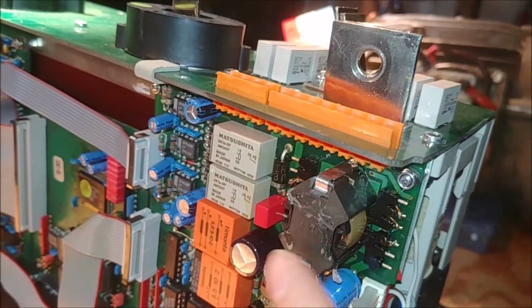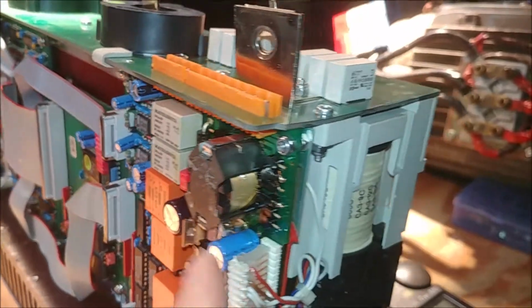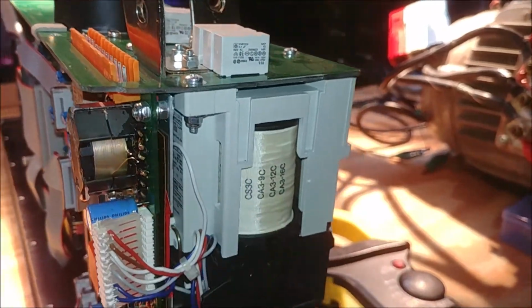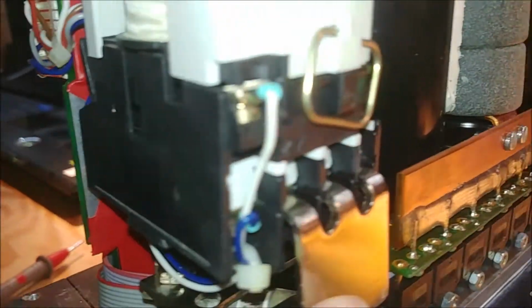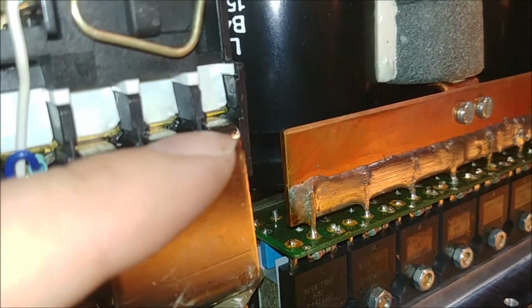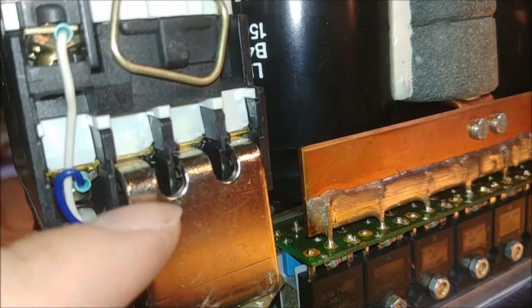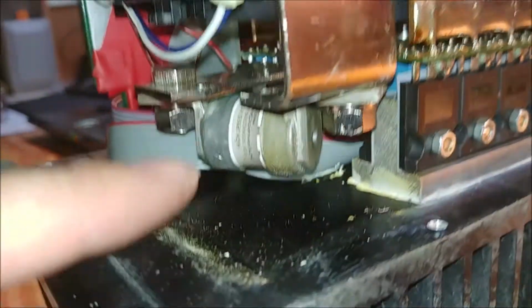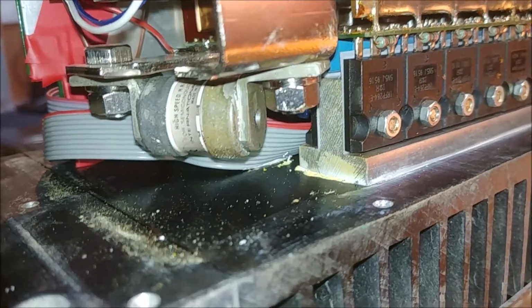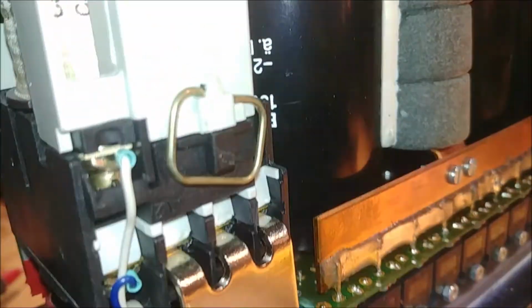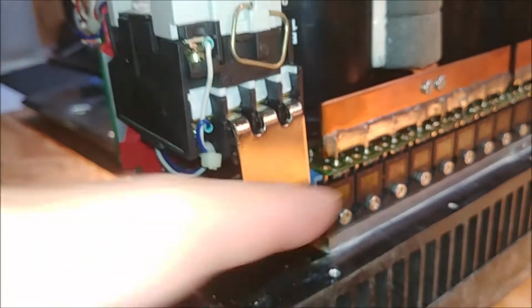So if this is running a little low, maybe it didn't have enough power to hold the contactor in, which caused the contacts to not quite make a good enough connection, causing them to overheat, which then causes the fuse to die. I checked all of the bridges.